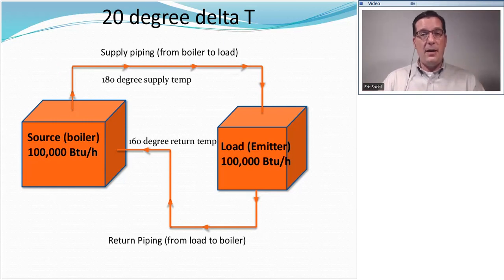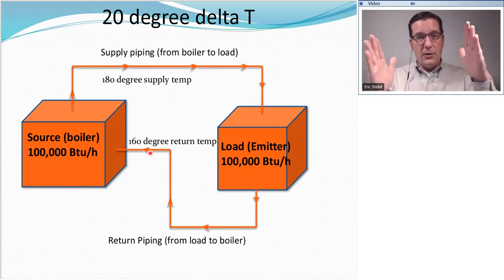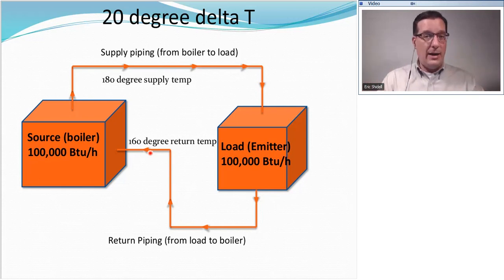As the water rushes through the emitter quickly, it doesn't have much of an opportunity to release its heat into the conditioned space. The way we solve that problem is, number one, we measure the supply water temperature and we measure the return water temperature. And if those two temperatures are too close together, what we need to do is slow the water flow down until we reach that 20 degree difference.